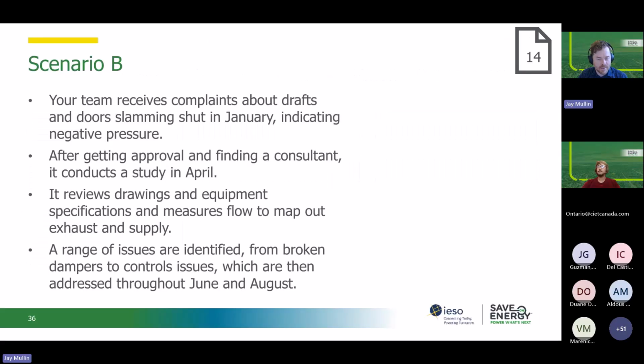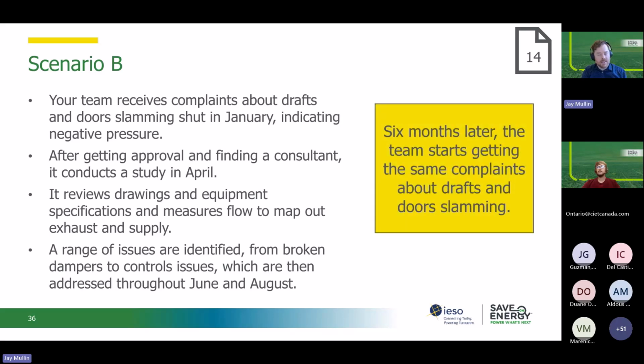All right, we've got our next scenario. Scenario B. Your team receives complaints about drafts and doors slamming shut in January, indicating negative pressure in the facility. You take this to management, you get approval to conduct a study, and find a consultant. By the time all that's done, it takes place in April. The study reviews the drawings and equipment specifications. They do measure flow, and map out exhaust and supply. A range of issues are identified, from broken dampers to control issues, which are then addressed through June and August. But 6 months later, the team starts getting the same complaints about drafts and doors slamming.